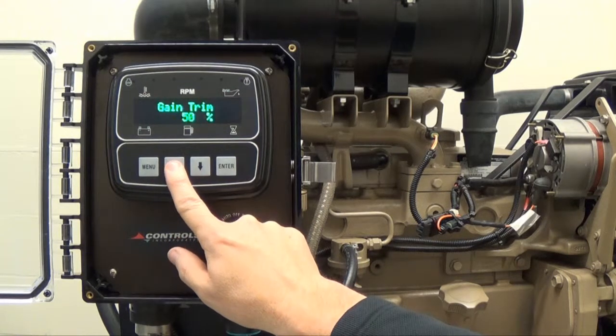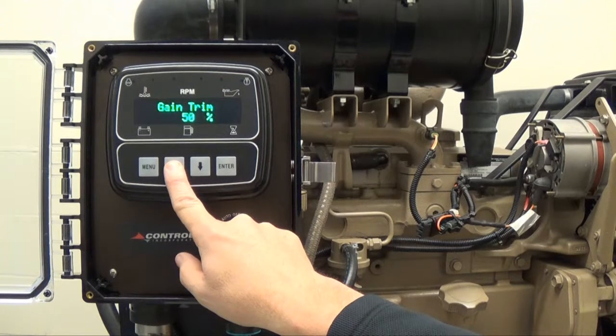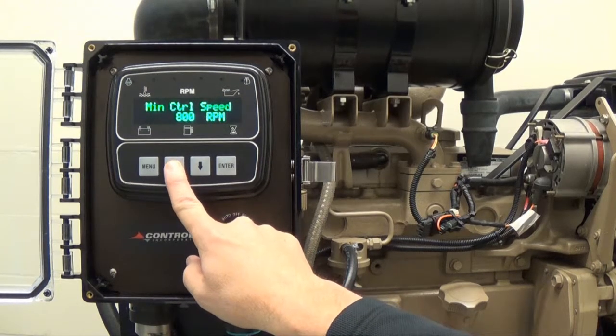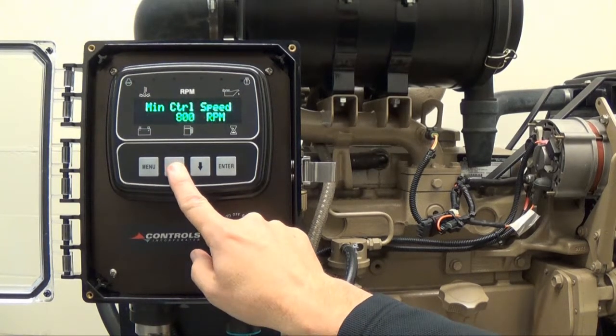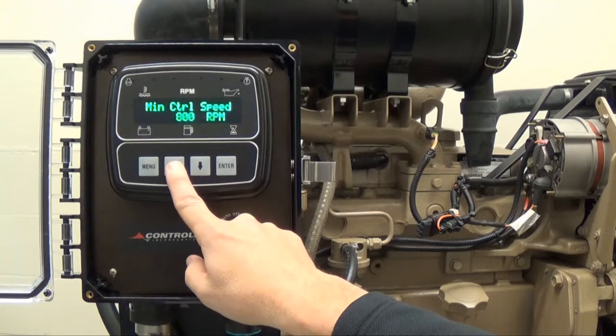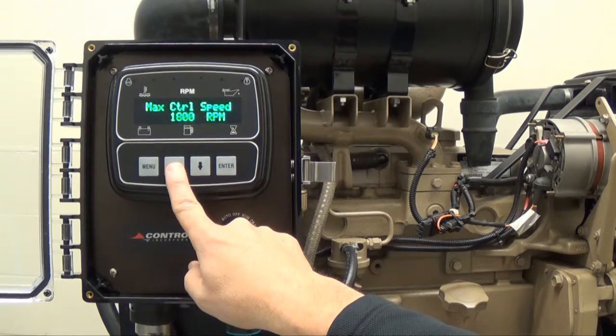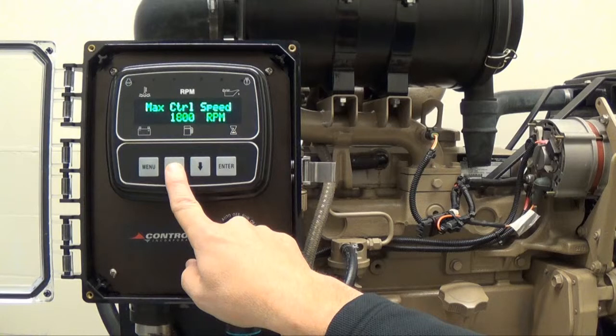Press the up arrow button to view the gain trim, which is currently set to 50%. The operator can increase or decrease throttle reaction response time by adjusting the gain trim setting. In this video, the operator chooses to leave it set to 50%. Press the up arrow button to view the minimum control speed, which is currently set to 800 RPM. Press the up arrow button to view the maximum control speed, which is currently set to 1800 RPM.